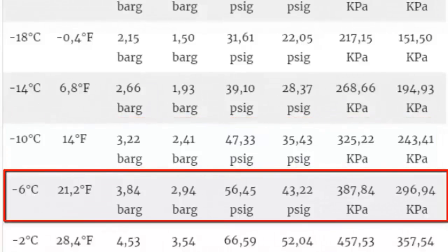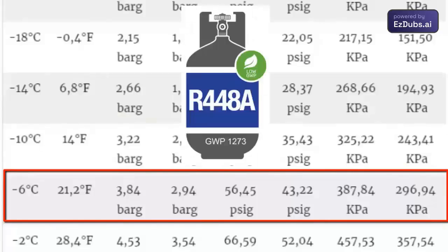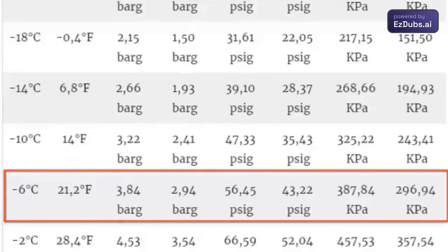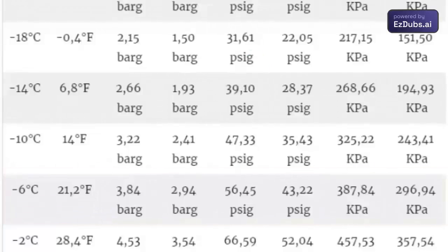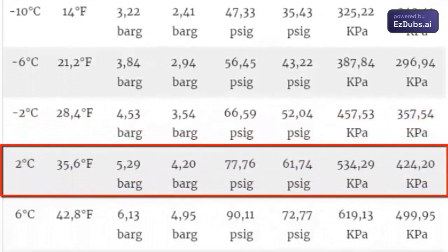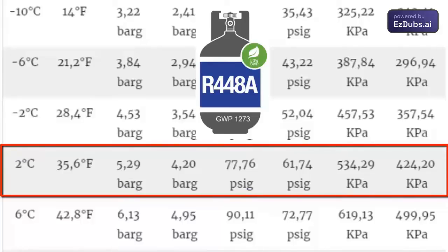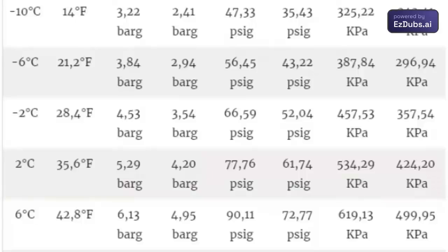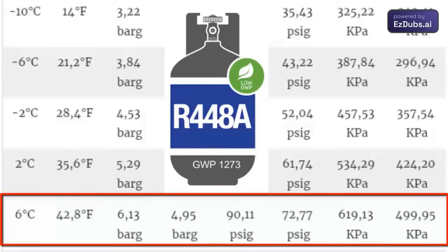4. To achieve minus 6°C (21.2°F) in the evaporator, a low gauge pressure of 2.94 bar, equivalent to 43.22 psi or 296.94 kPa is needed. 5. To achieve minus 2°C (28.4°F), a low gauge pressure of 3.54 bar, equivalent to 52.04 psig or 357.54 kPa is needed. 6. To achieve 6°C (42.8°F), a low gauge pressure of 4.95 bar, equivalent to 72.77 psi or 499.95 kPa is required.